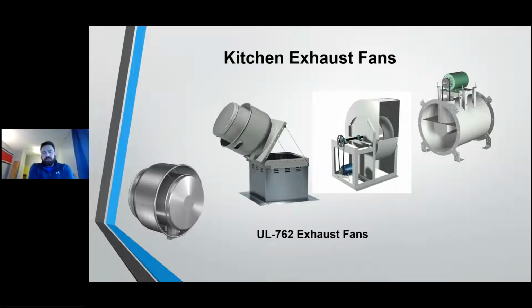Utility set fans are another option when it comes to UL 762 fans. This particular utility set fan, this rendering, is actually for a UL 705 fan. So if you remember, that's for a dishwasher or a heat-only hood. All UL 762 fans need to be of an upblast configuration so that you're not dumping grease back onto your roof deck or straight across, as this utility set fan would be.